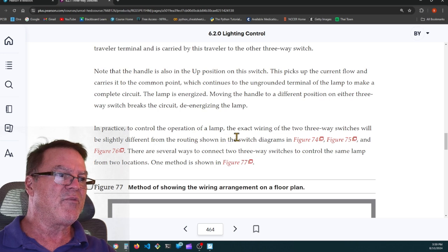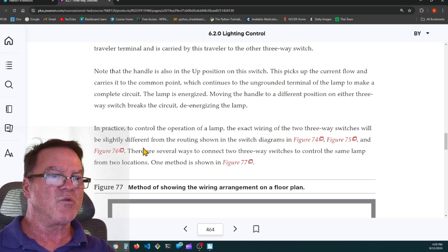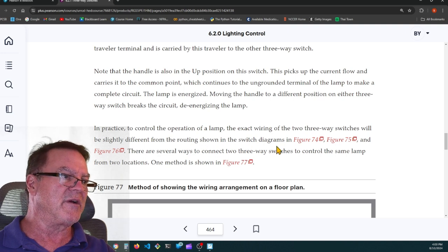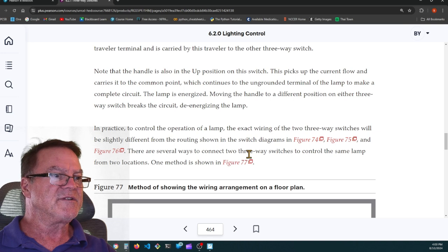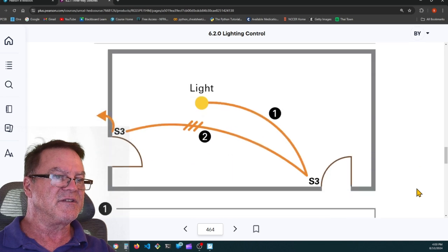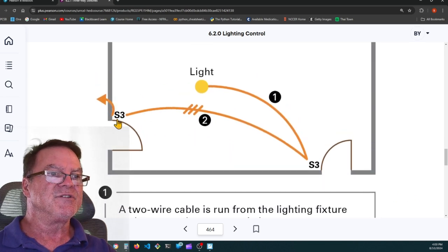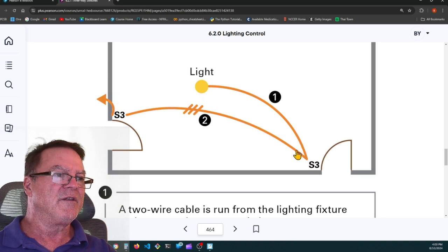In practice, to control the operation of a lamp, the exact wiring of the two three-way switches will be slightly different from the routing shown in the switch diagram. There are several ways to connect two three-way switches to control the same lamp from two locations. The method is shown in figure 77. So on this, they'll have three conductor running between the two three-way switches with the home run coming from one of the three-way switches. So you have a black coming in with a white. The white is just going to travel through the switch, not connected to the switch, and going to the light. Then the black and the red conductors will be the travelers between the two three-way switches.